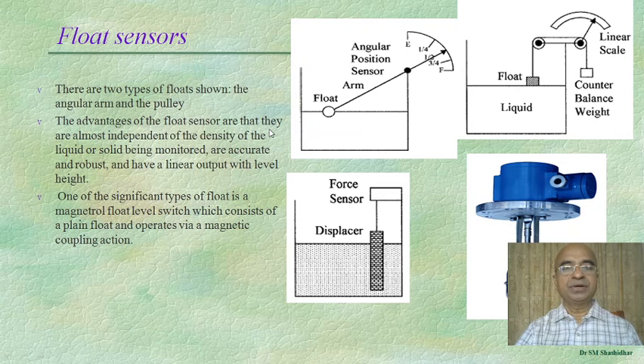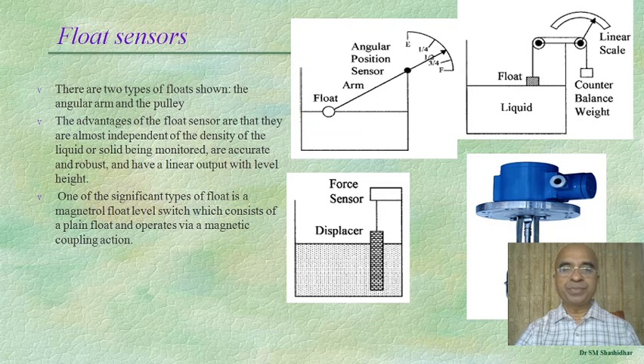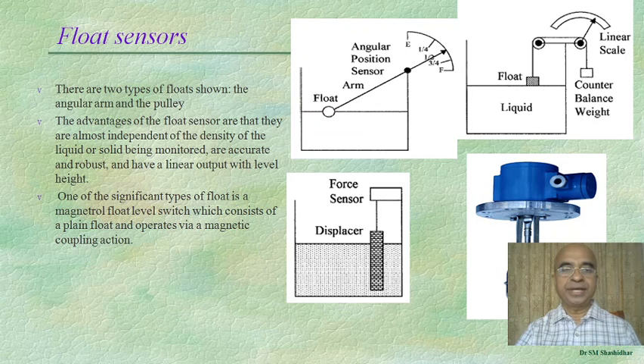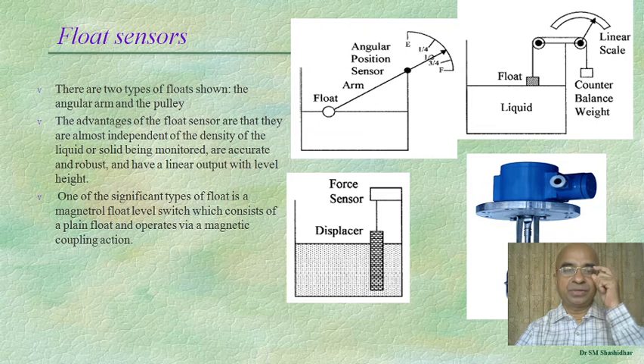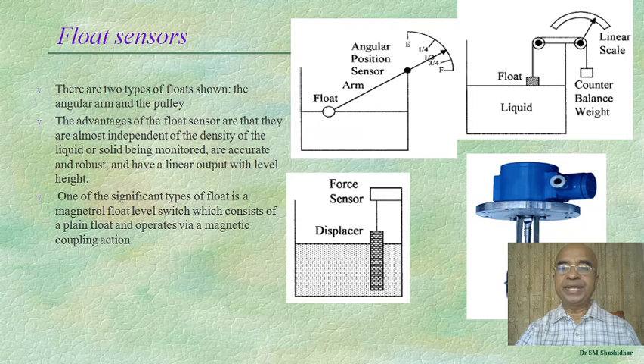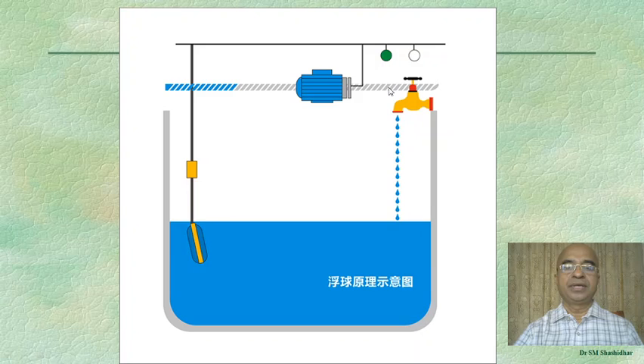The advantages of float sensors are that they are almost independent of the density of the liquid or solid being monitored. They are accurate, robust, and have a linear output with level height. One significant type is the Magnetrol float level switch, which consists of a plain float and operates via magnetic coupling action.